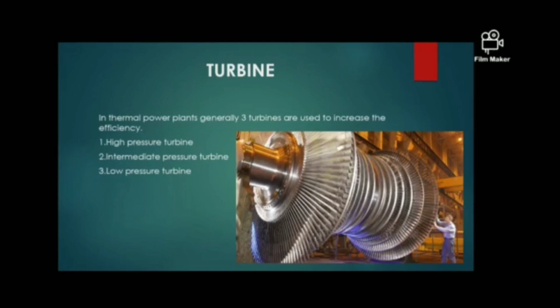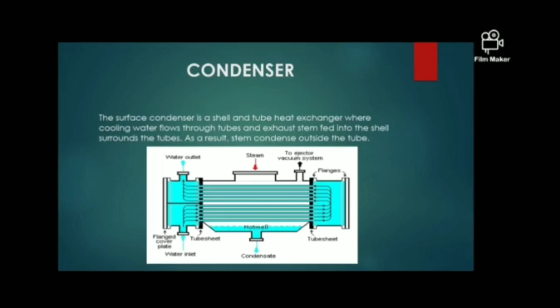The surface condenser is a shell and tube heat exchanger where cooling water flows through the tubes and exhaust steam is fed into the shell surrounding the tubes. As a result, steam condenses outside the tubes. Here is the diagram of a condenser.